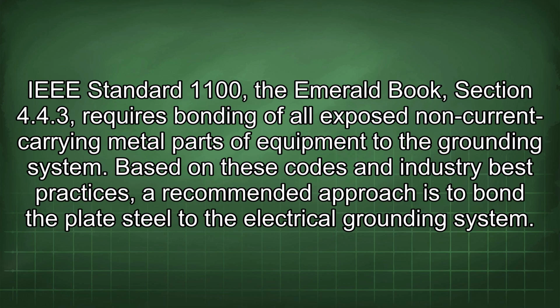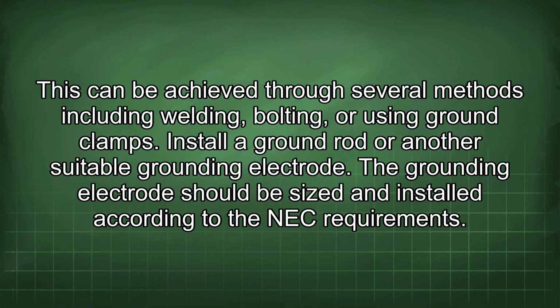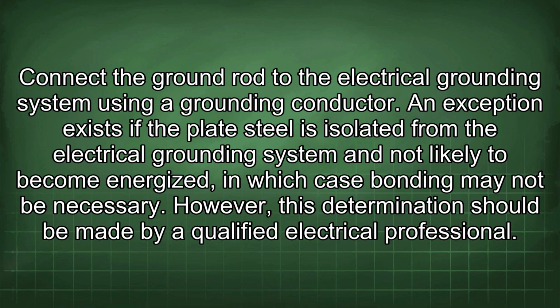IEEE Standard 1100, the Emerald Book, Section 4.4.3, requires bonding of all exposed non-current carrying metal parts of equipment to the grounding system. Based on these codes and industry best practices, here are recommended approaches to bond the plate steel to the electrical grounding system. This can be achieved through several methods including welding, bolting, or using ground clamps. Install a ground rod or another suitable grounding electrode. The grounding electrode should be sized and installed according to the NEC requirements. Connect the ground rod to the electrical grounding system using a grounding conductor.